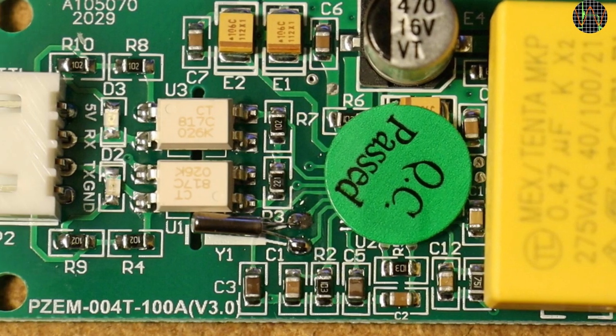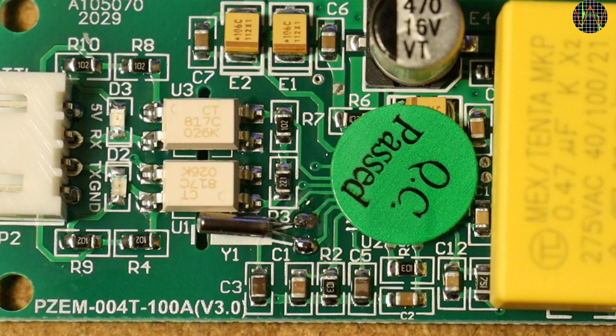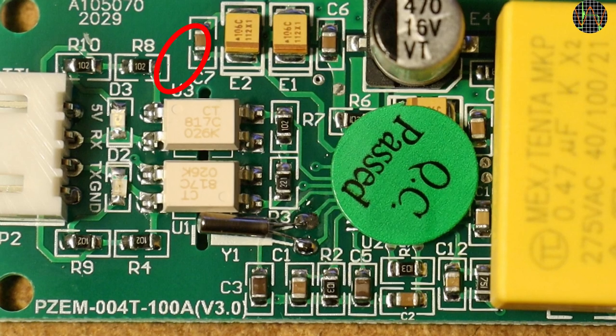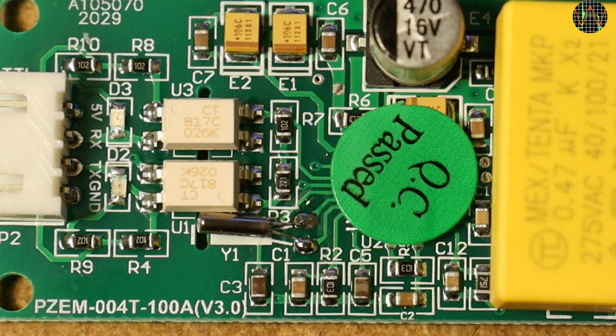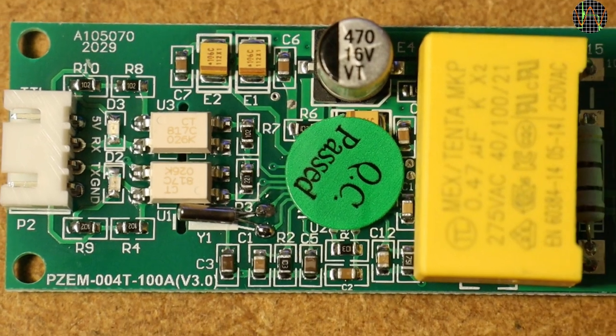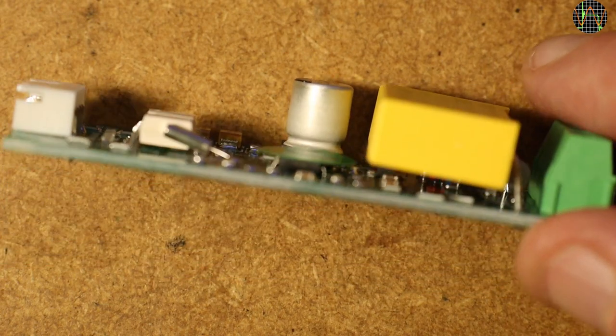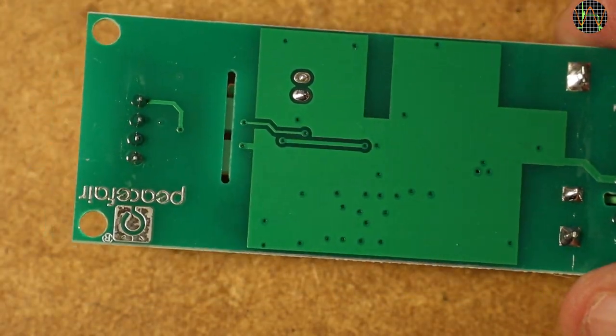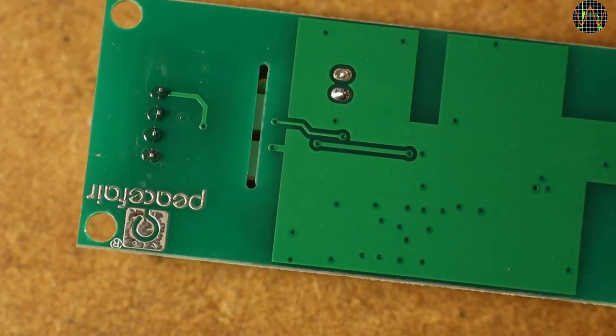The two white blocks are indeed optocouplers and the separation would be excellent except this corner here, where there is just a 3 mm gap between mains reference C7 and R8, which is part of the serial interface. If only they had just moved C7 slightly higher or R8 lower. There's room to do that. Sometimes you just have to wonder what they were thinking.